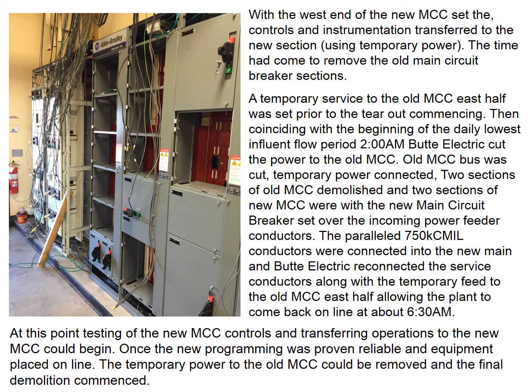A temporary service to the old MCC was set prior to the tear-out commencing. Then coinciding with the beginning of the lowest daily influent flow period, at 2 a.m., Butte Electric cut the power to the old MCC. Old MCC bus was cut, temporary power connected, 2 sections of the old MCC demolished, and 2 sections of the new MCC with the new main circuit breaker set over the incoming power feeder conductors. The paralleled 750,000 circular mil conductors were connected into the new main, and Butte Electric reconnected the service conductors along with the temporary feed to the old MCC east half, allowing the plant to come back online at about 6:30 a.m.